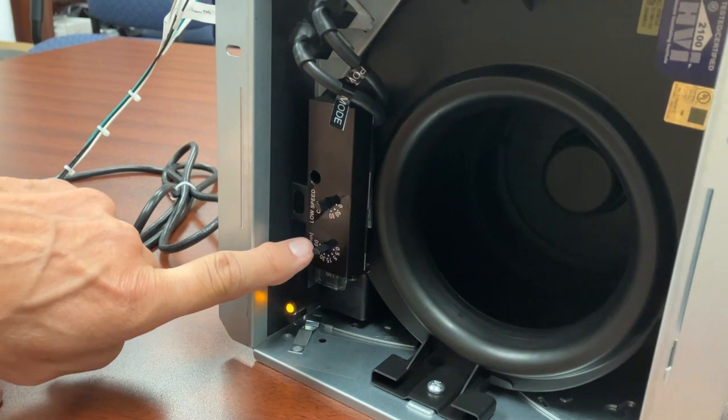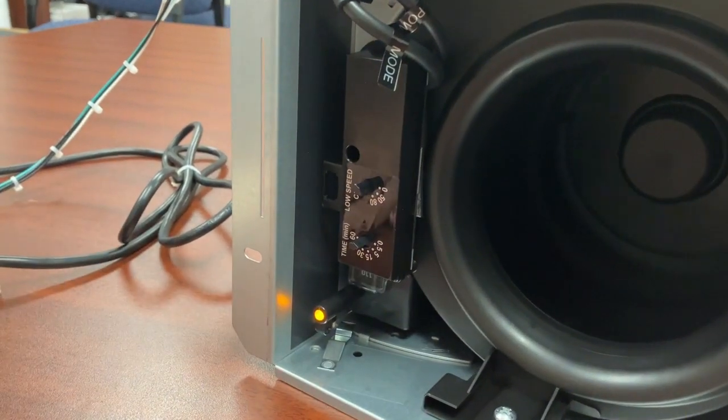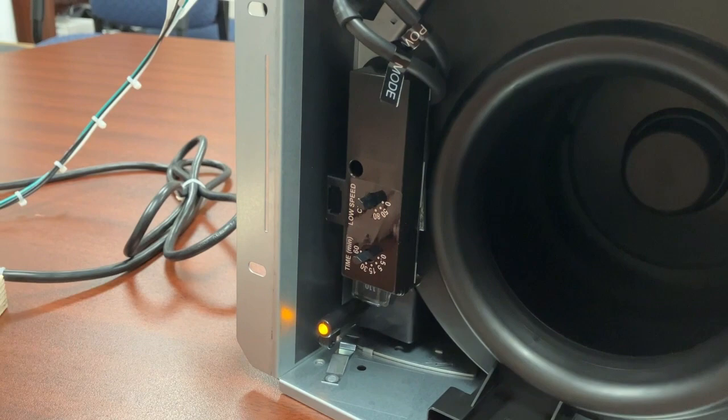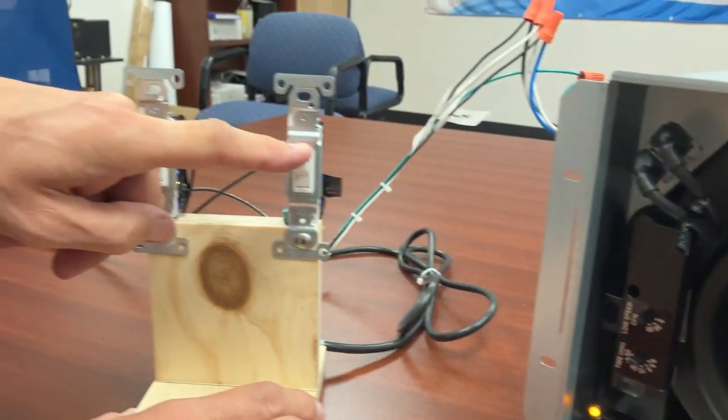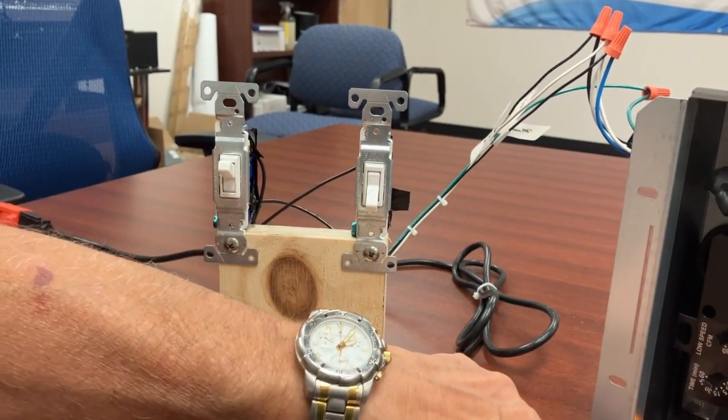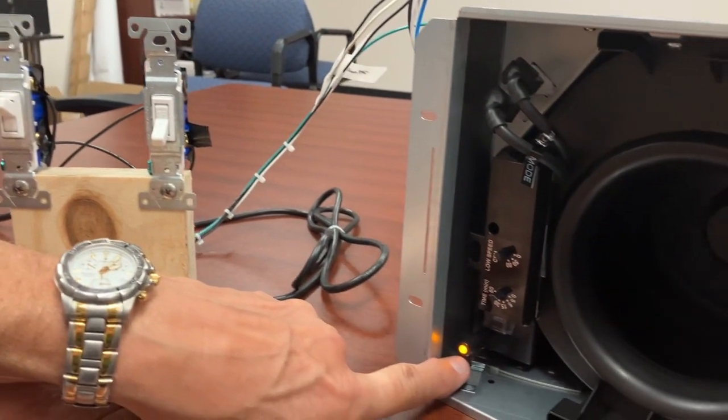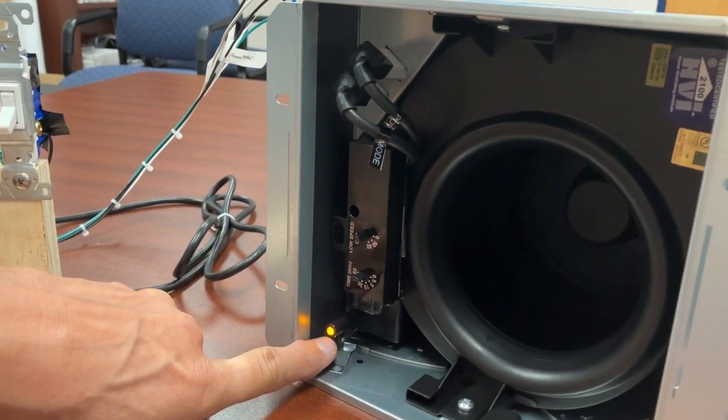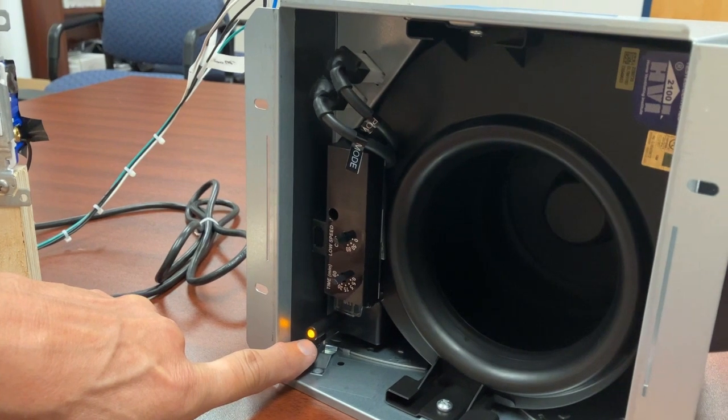Okay, and this is our delay hold. Right now I have it set for a half a minute. So when I shut this switch to the off position, it's going to hold the boost for 30 seconds. And once the 30 seconds is completed, the LED will transition to green.